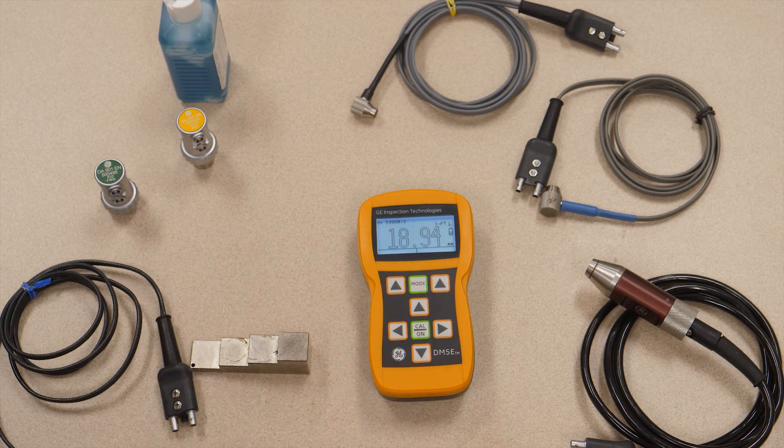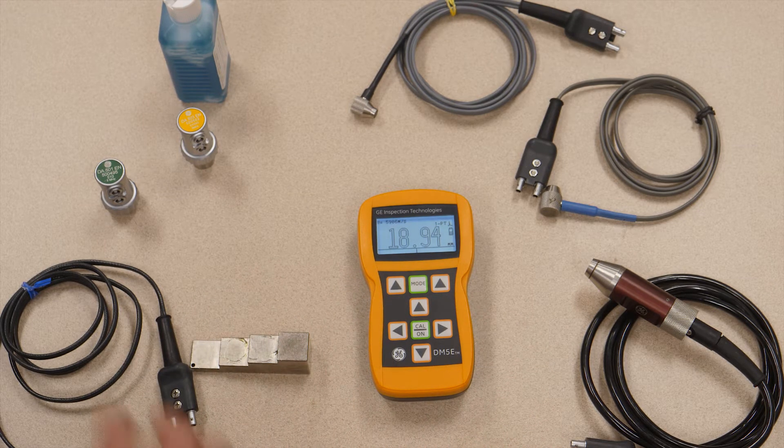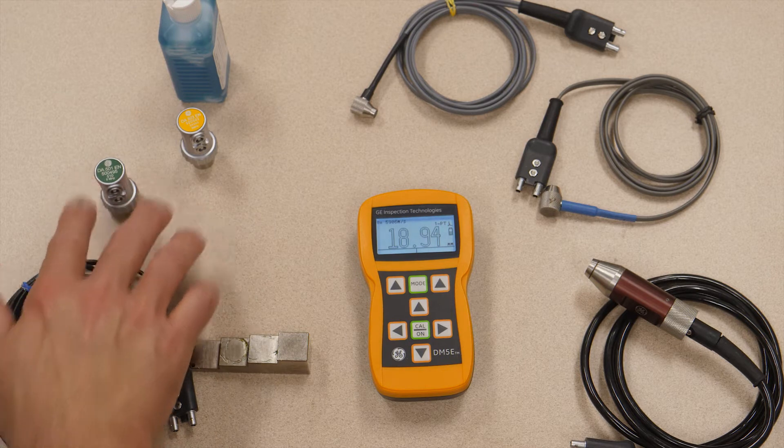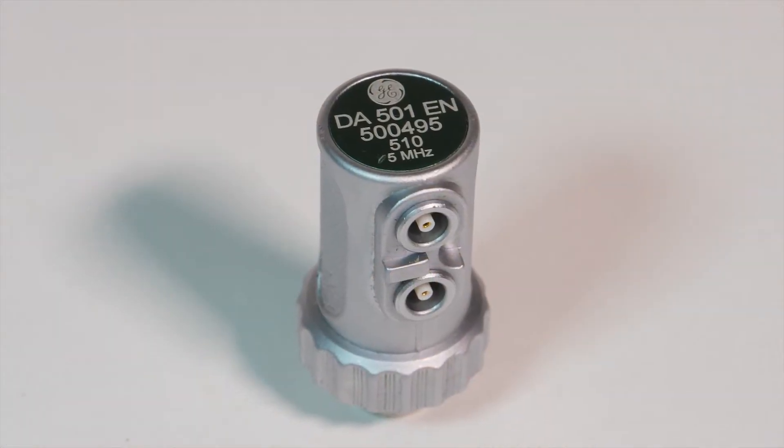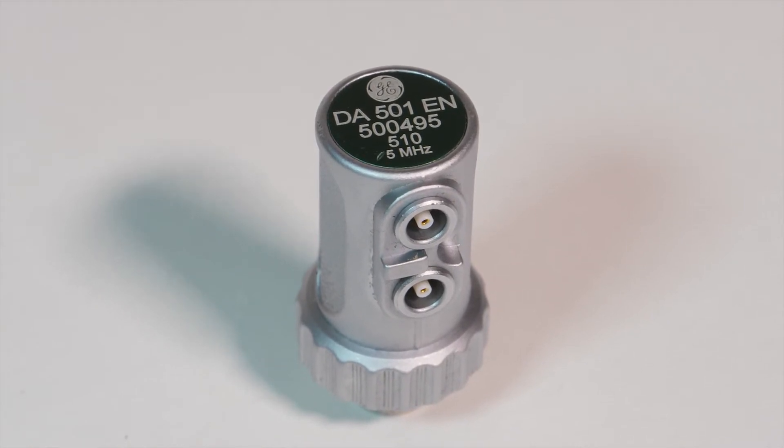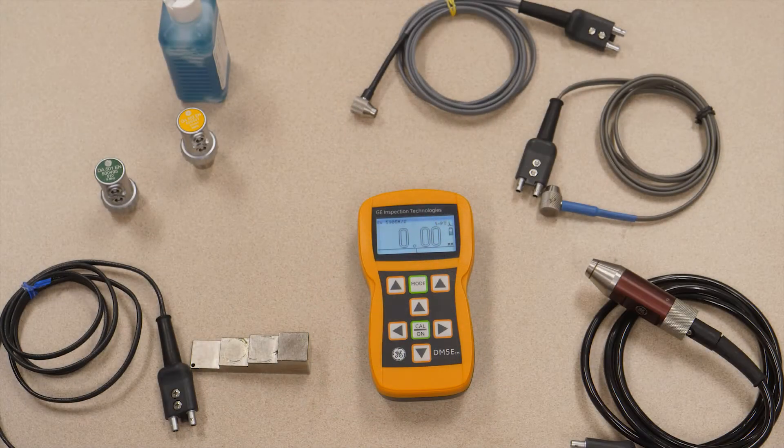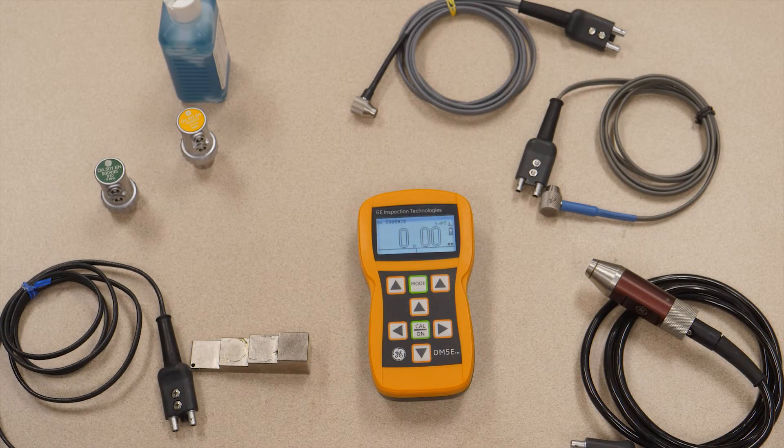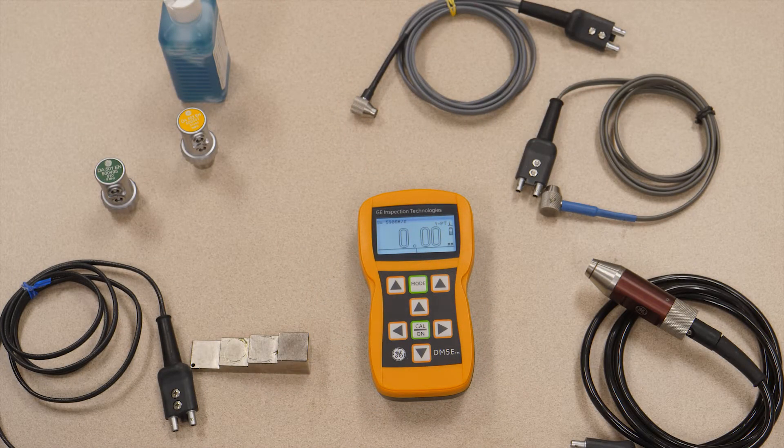Shown with the instrument here are some of the most common probes. The DA501 is probably the most commonly used probe with the DM5E. It is a five megahertz general purpose probe with a measurement range of about one millimeter to two hundred millimeters, forty thousandths of an inch to eight inches.